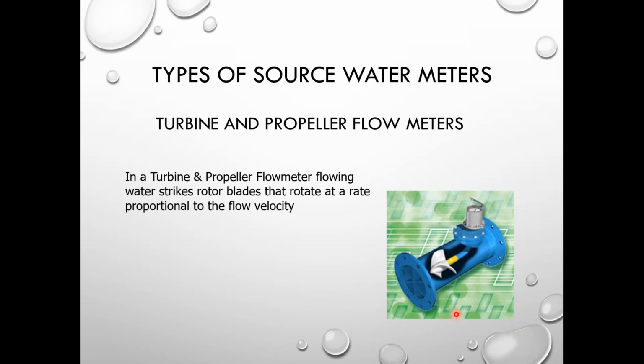So we're making these meters a little bit smarter in that range. These meters also run at what we call a 10-to-1 turn down ratio. So if my meter runs at the low end at 30, so it starts reading and the impeller starts turning at 30 gallons a minute, the maximum it'll run would be 300. So that's what I mean by a 10-to-1 turn down ratio.